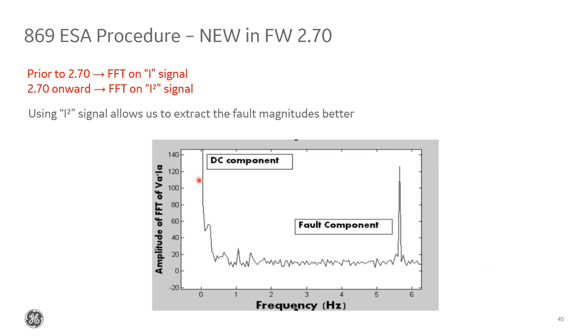A new shifted fundamental signal shows up at 2 times the line frequency. And what we're left with are the harmonics in the signal, shown to the left of that, 2 times the fundamental frequency. So it looks something like this, where at 0 hertz at DC, you see a spike for the fundamental. Somewhere along here, you would see the 2 times fundamental, which isn't shown. But if a fault were to occur, we could see that fault component spike much, much more magnified.